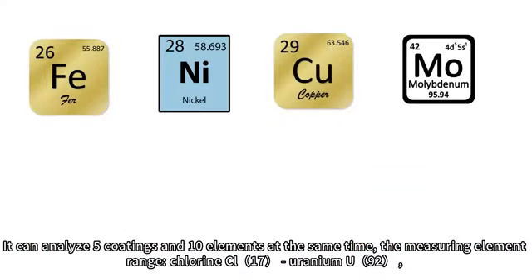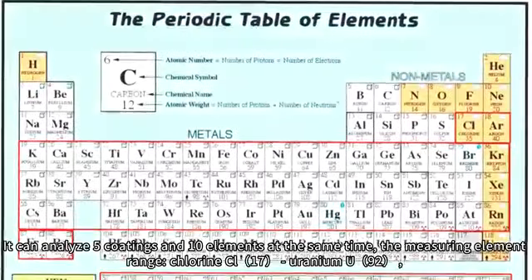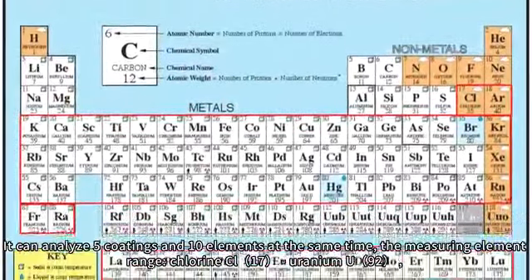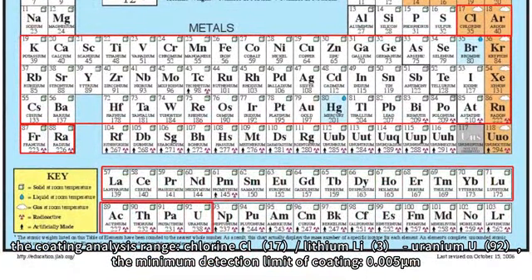It can analyze 5 coatings and 10 elements at the same time. The measuring element range is chlorine (Cl) to uranium (U), and the coating analysis range is chlorine (Cl), lithium (Li), to uranium (U).